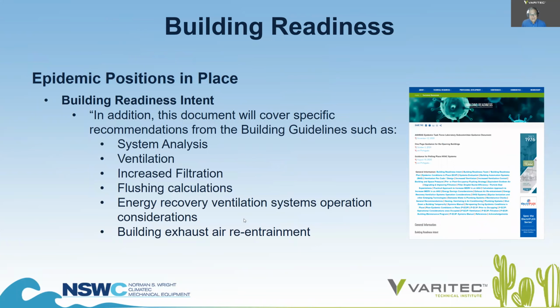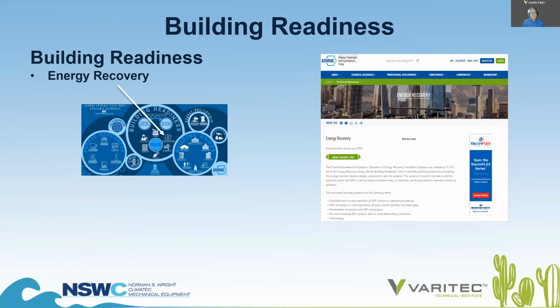The Building Readiness Intent goes on to say that it offers specific recommendations from the building guidelines, such as how do you do system analysis? How do you evaluate your ventilation? Are you getting adequate ventilation to the space? How do you do increased filtration? How do you calculate the duration of flush modes so you evacuate any buildup of pathogen concentrations through the occupied hours? It looks at energy recovery ventilation system operation and any potential for exhaust air reentrainment.